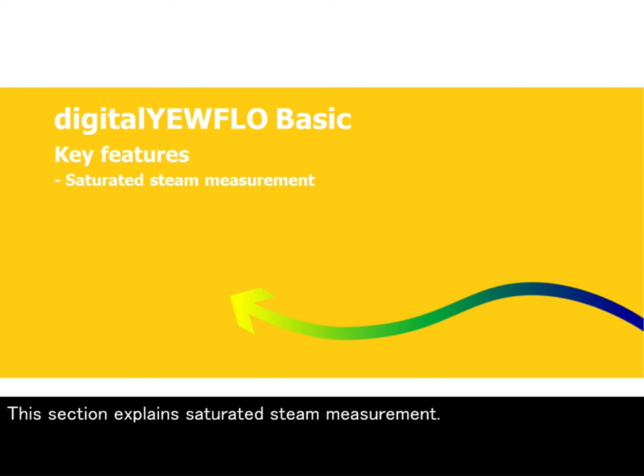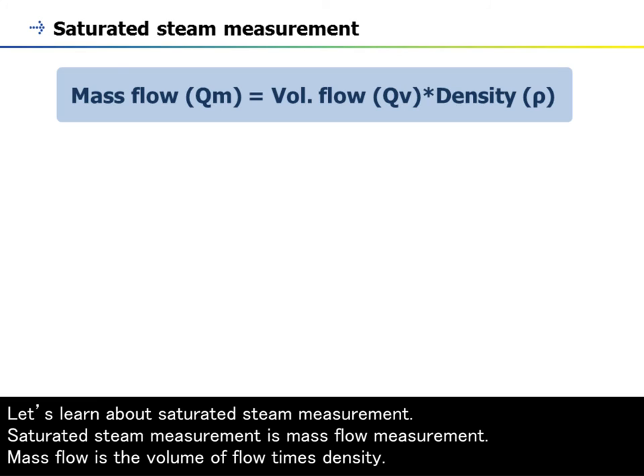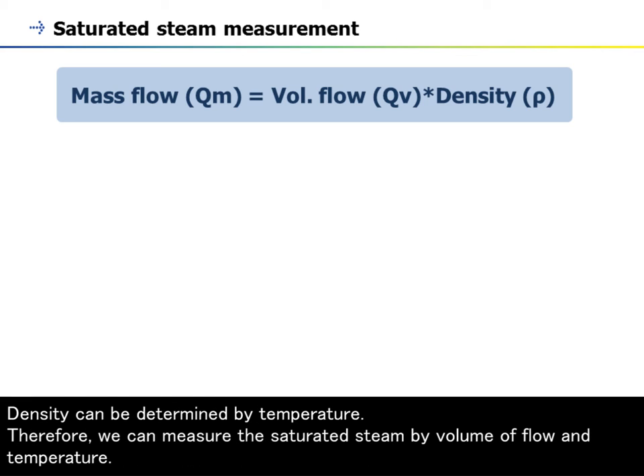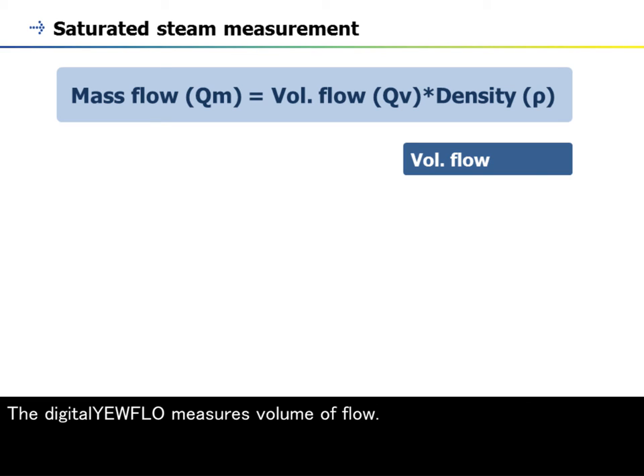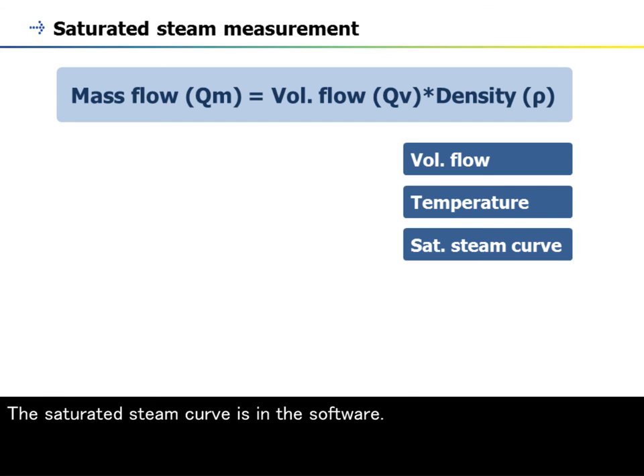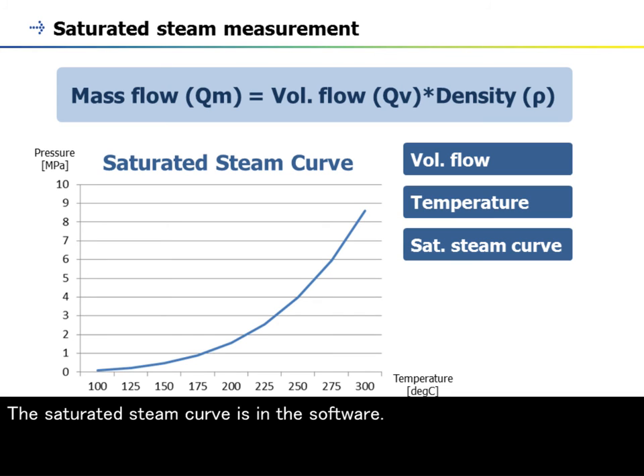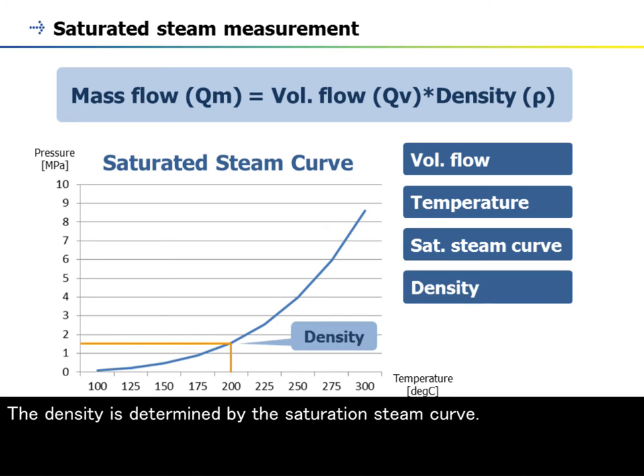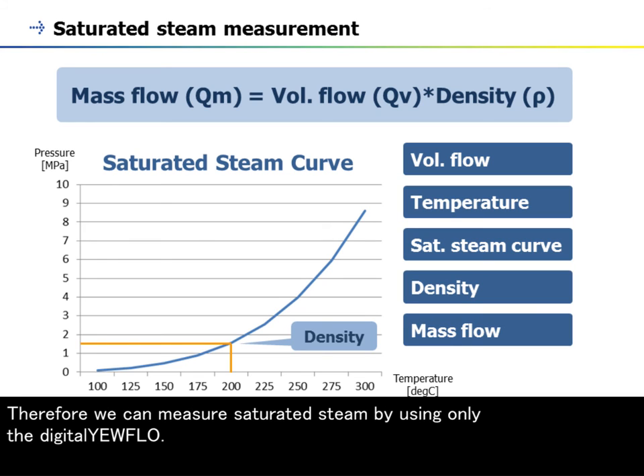This section explains saturated steam measurement. Saturated steam measurement is mass flow measurement. Mass flow is the volume of flow times density. Density can be determined by temperature. Therefore, we can measure the saturated steam by volume of flow and temperature. The digitalYEWFLO measures volume of flow. A built-in temperature sensor measures temperature. The saturated steam curve is in the software, and the density is determined by the saturation steam curve. Therefore, we can measure saturated steam using only the digitalYEWFLO.